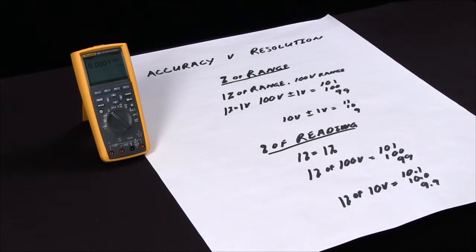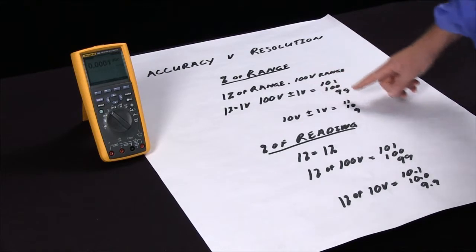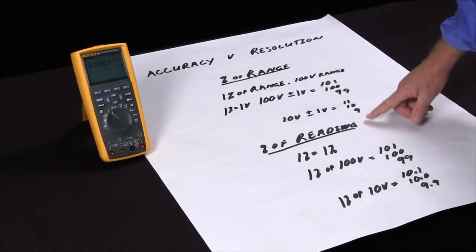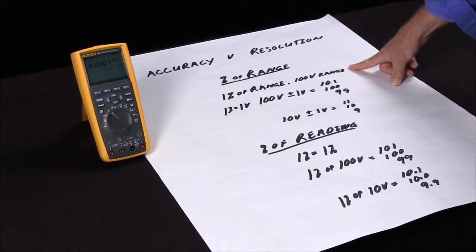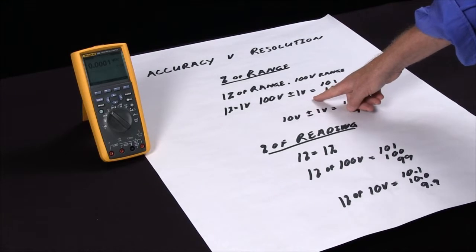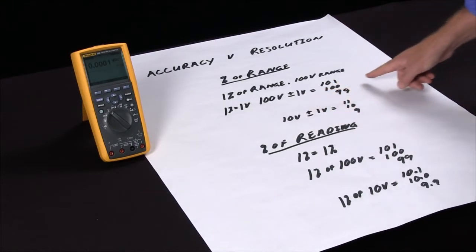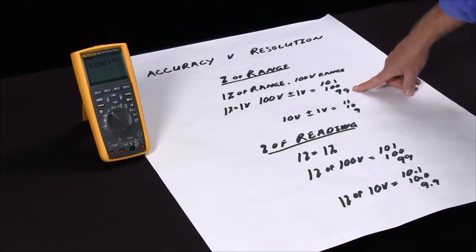So there's two ways we have accuracy specified. One is in percent of range and one is in percent of reading. For percent of range, if we have a one percent specification of range and we're on a hundred volt range, one percent of a hundred volts is one volt. So that means with a reading of a hundred volts that can be within specification at plus or minus one volt, so a reading between a hundred and one and ninety nine is actually a good reading on this meter.